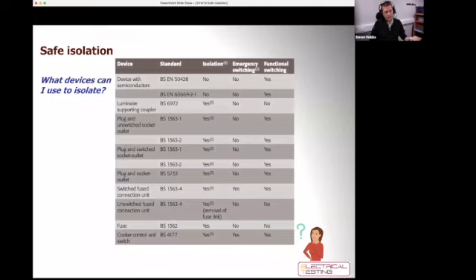That table continues. And again, as we can see here, sort of halfway down, plugs and sockets can be used for isolation. So we can see halfway down, plugs and switch socket outlets, and the third column along, isolation generally, got a yes there. So plugs and sockets can be used for isolation. Maybe in some highway situations, that's a viable option rather than isolators and the like, isolating devices.